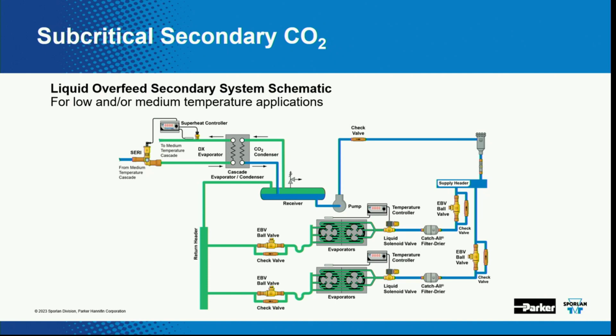What you're going to have is you have to define your overfeed rate. For this scenario, it might be a 2 to 1 overfeed - you're sending 2 units of liquid CO2 in and getting 1 out. That's similar to ammonia, you might use like 3 to 1, because you have a compressor sucking, so you need to have that vapor - you'll have about a 3 to 1 ratio on the recirculating. So your evaporators, when you have wet suction coming back, you'll have 3 parts liquid and 1 part vapor.